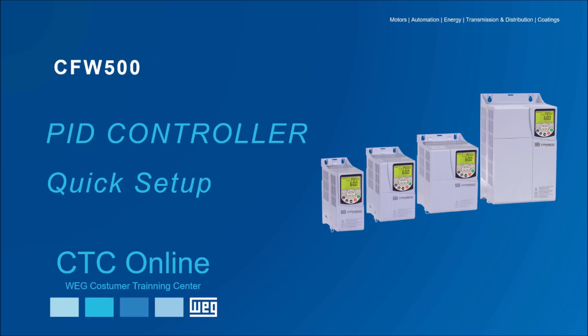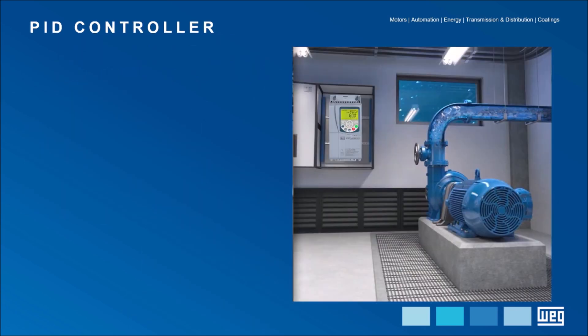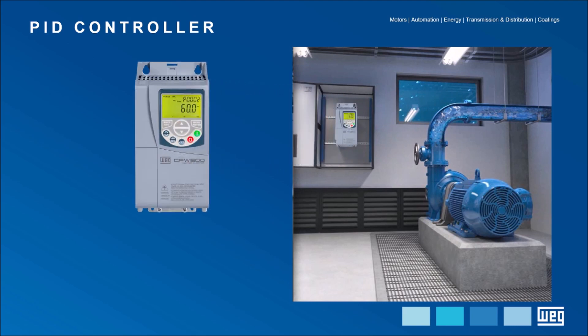Hello everyone. In this video lesson we will demonstrate how to enable and set the PID controller in the CFW500 series frequency inverter. The use of this type of control in the inverter creates process stability and promotes energy savings in several applications when required — level, pressure, flow, and temperature control. Many inverters already have this regulation method built in, and that is the case with the CFW500.